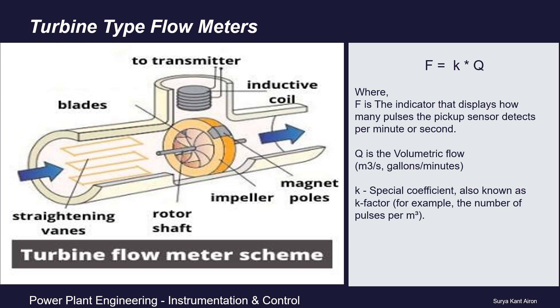Another important part worth mentioning is the straightening vanes. At the inlet side of the flow meter there are parallel horizontal plates — these are straightening vanes — and their purpose is to evenly distribute the stream jet across all the blades. Mechanical stabilizers are also mounted in the structure to avoid flow turbulence. The frequency with which these changes occur is monitored and sent to the transmitter, and this frequency is directly proportional to the flow velocity.